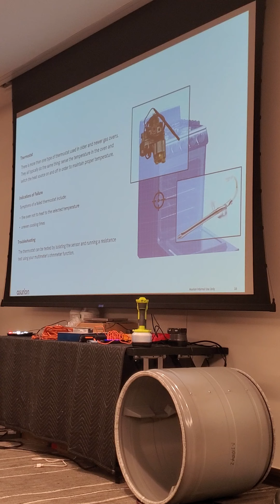Safety valves. You have your gas safety valve, okay? It works in conjunction with the control board and the thermostat. All right? The only other thing that happens is when you initially turn it on, it's looking for the amperage coming back to the control board from your igniter to initially open that valve. Once that's done, it gets up to temp, the thermostat takes over, and it controls it from there. Okay, does everybody understand how that flows, how that works?